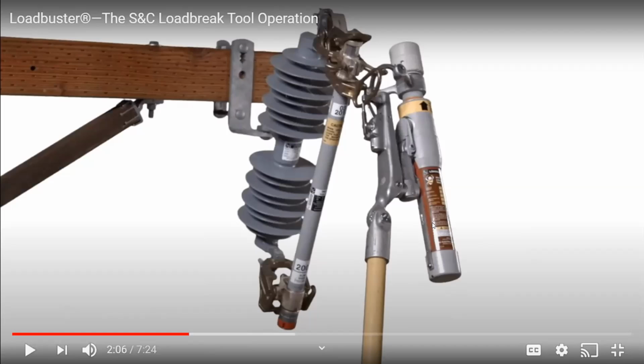So you're out there in the field and you're using this thing regularly and you're breaking 50, 100, 200. I mean, the thing will last pretty much forever. You start breaking 900 amp loads or around that area, 900, 800 amp loads, you might want to take it apart and inspect it every so often.